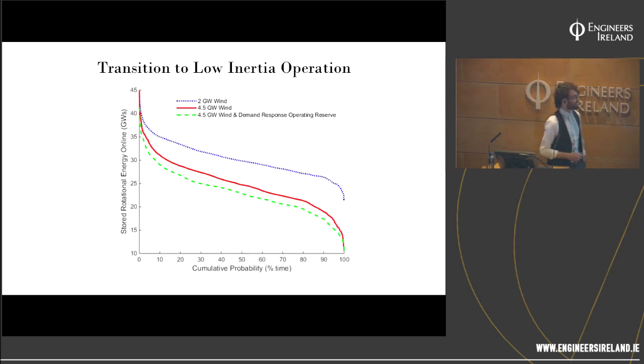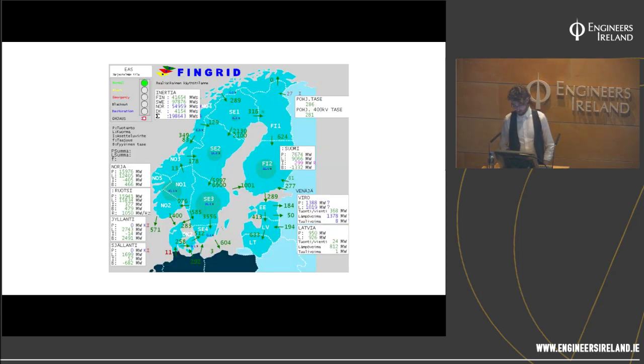So inertia is falling. We need to start monitoring it. We do it here, but they also do it in the Nordic system, and in the control room they monitor the inertia of the system. Now this is just the sum of the generators. The load will have an inertia as well.